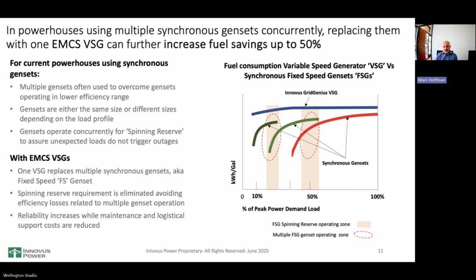Now let's talk about the powerhouses. As alluded to before, you have a genset that's most efficient at high loads, high demands. But what happens is loads, not just seasonally but daily, go up and down. They rise a bit in the morning, drop off maybe in the middle of the day, and rise at night. The more remote and northern the communities are, the bigger the load swing between wintertime and summertime.